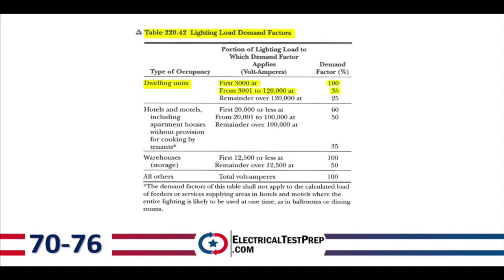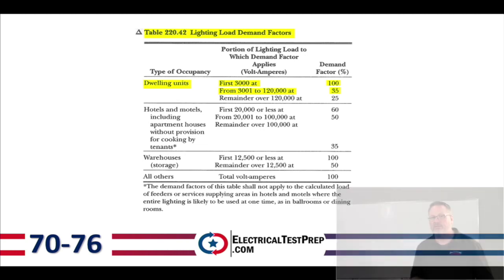Page 76 has a very important table — Table 220.42, Lighting Load Demand Factors. We take our square footage and rate it using this table. Both the square footage and the small appliance and laundry loads can be derated using this table. For a dwelling unit, it includes the lighting and general receptacle load, all incorporated in that 3 volt-amps per square foot.